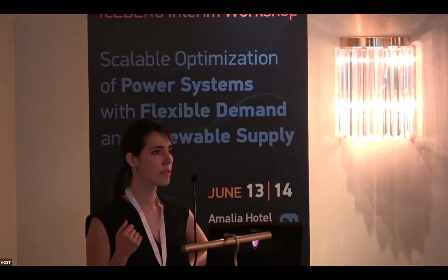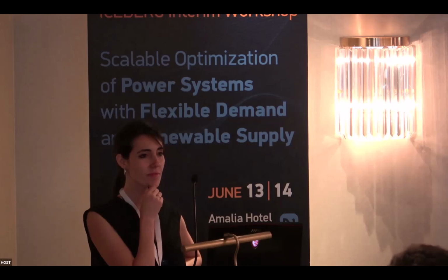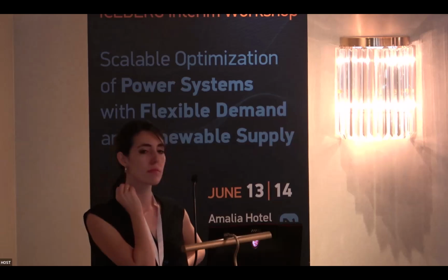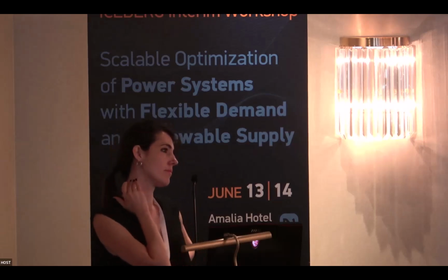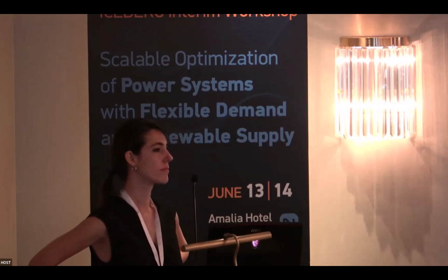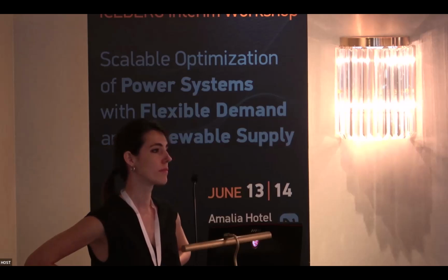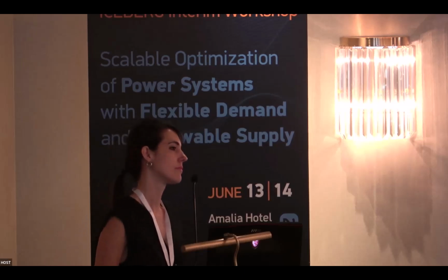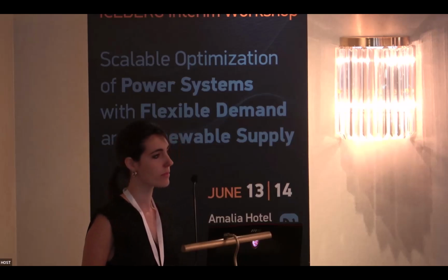Okay. So I think the formula you have in mind is CONE equals VOLL times LOLE. So that's a super simplified approximation of the optimal solution for a single zone setting. Once you have interacting zones and you pose the same question of what is the optimal expansion subject to some LOLE constraints, then there are intricate effects of if you are about to shed load, how do you share that load sharing between different regions?